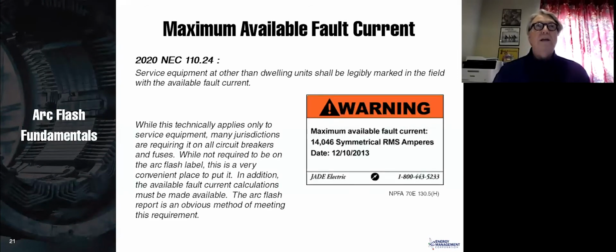Well, what we have found lately is that a number of inspectors are saying, that's fine, but we want a label on all of the equipment. So that's not a code requirement, but it tends to be required by a number of inspectors. And of course, since we have been required to do this on a number of jobs, we've decided, you know what, it's pretty simple to put that on the arc flash sticker, because when you do an arc flash study, you calculate the available fault current anyway. Why not? Why don't we just put it on the sticker and make it available?